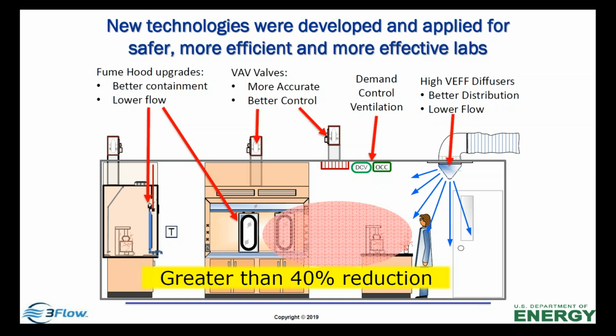The valves are now coming with flow sensing ability in them that actually works well, so that when we start talking about metrics and measurement and analytics, if you're not measuring it, then you don't know what you have. So the ability to measure and validate is very important. The valves have gotten a lot better over the years, and they're continuing to improve. Demand control ventilation is like an air quality system, if you will. It's basically a system that goes into a lab and takes samples of CO2 and other things in the lab itself, and brings it back to a central location. Air change rates in the lab are being minimized, maybe by time of day or whatever they might be. And then if there's an event that's been sensed with this VOC system, it brings the lab up to its highest level of supply, bringing air into the space.